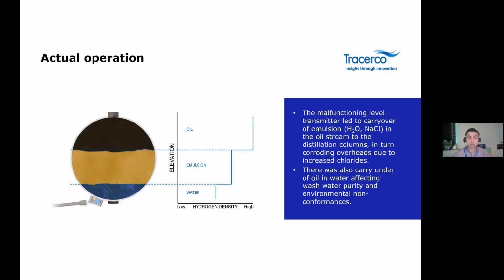During the scan, it was discovered that malfunctioning of the conventional level transmitter led to carryover of emulsion in the oil stream in the distillation column. In turn, this caused corroding overheads due to increased chlorides, and there was also carry-under of oil in the water, affecting water purity and causing environmental non-conformances.